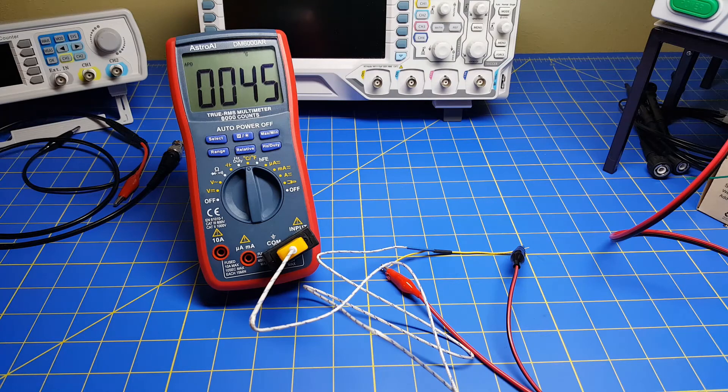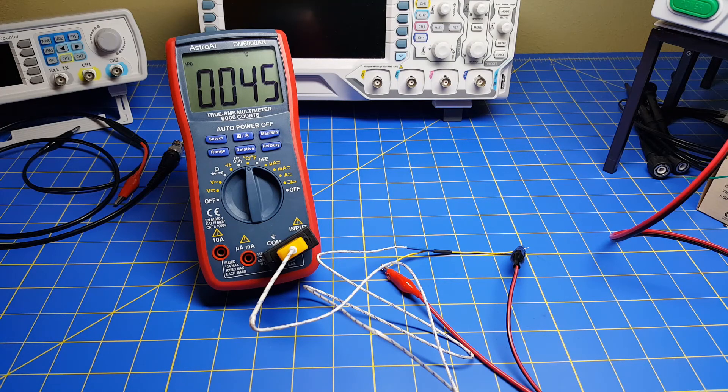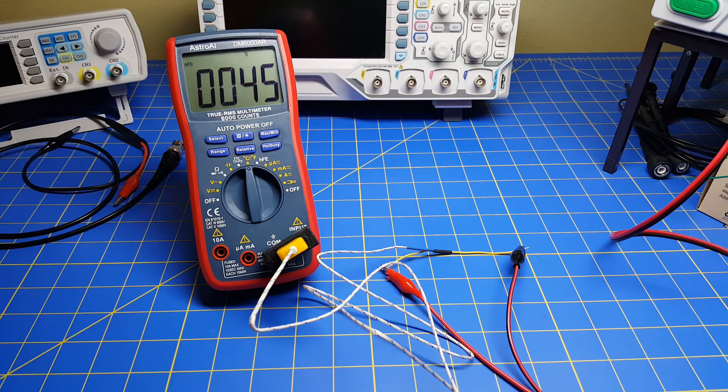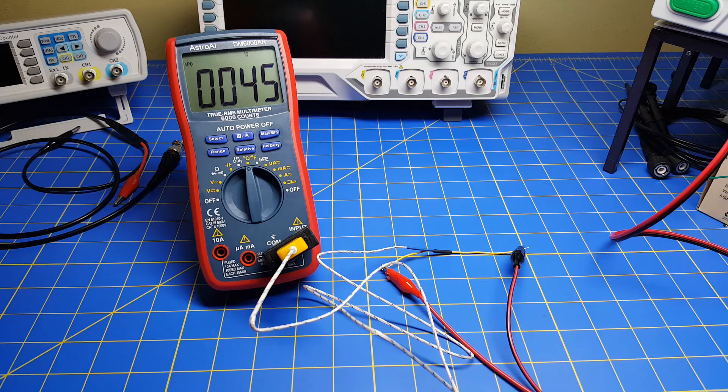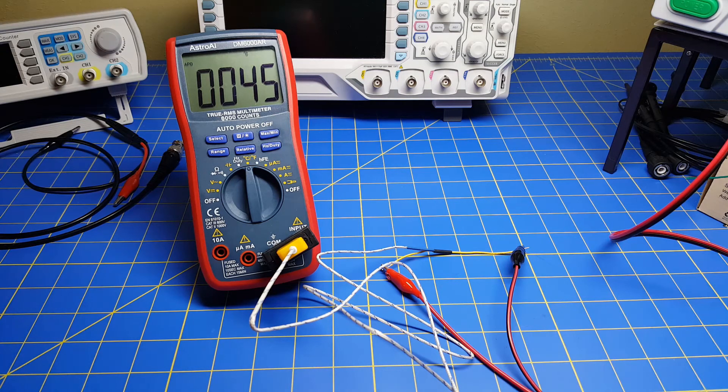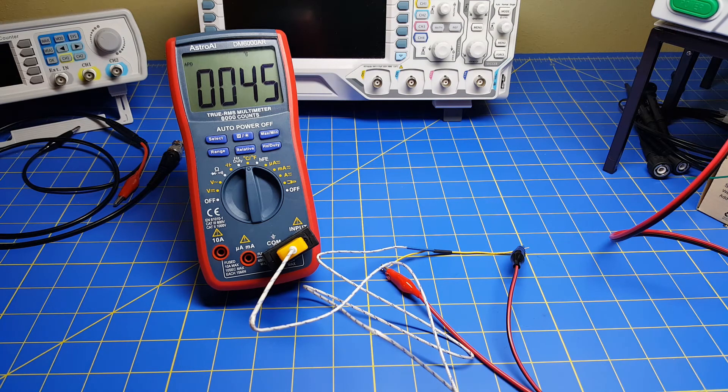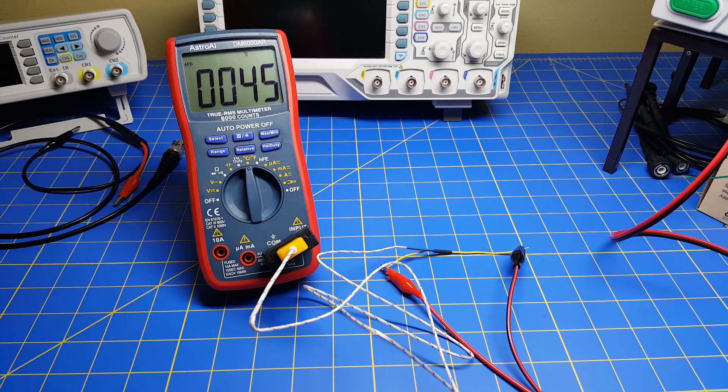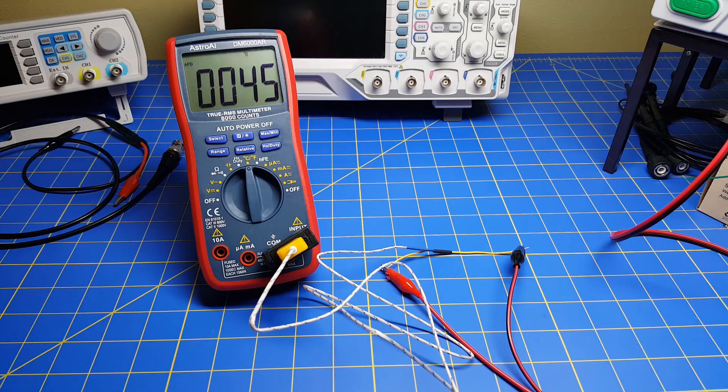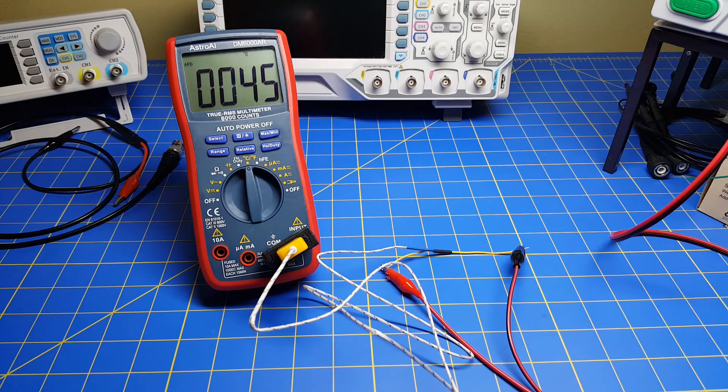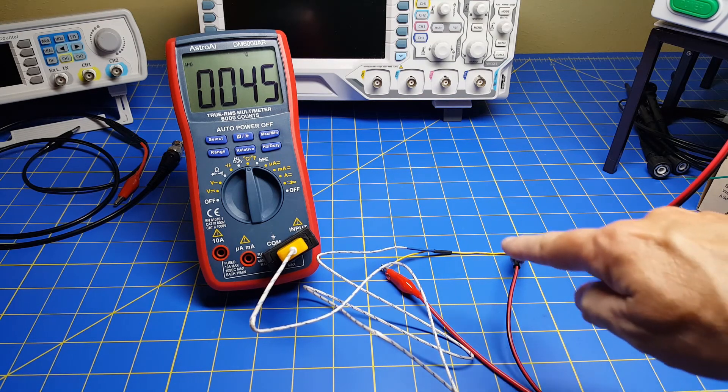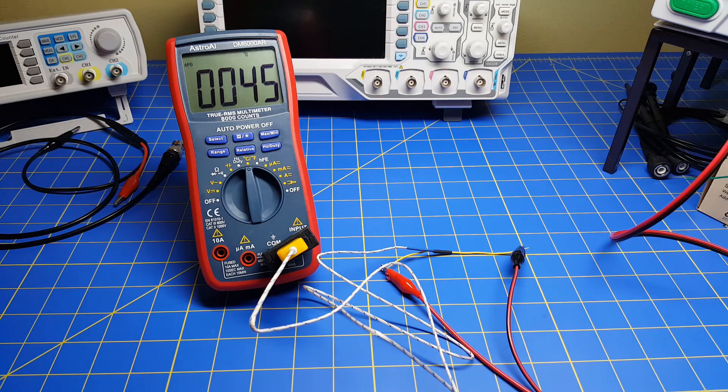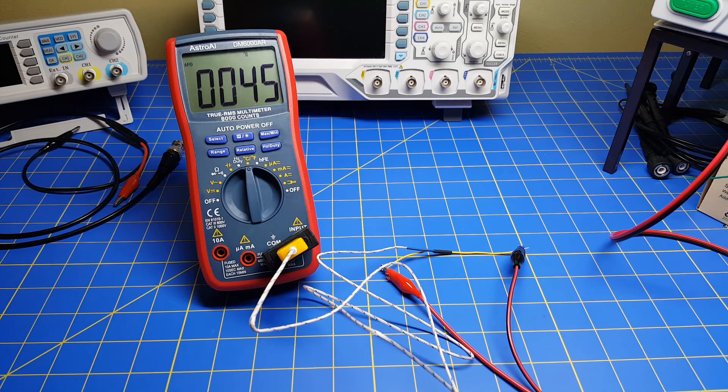Okay, so here we are after about 4 minutes or so. And the temperature has pretty much flattened out around 45 degrees centigrade. Once in a while it bounces up to 46. But, as you can see, it's nowhere near the 80 degrees C that the 8 amps are supposed to give you, which is the rating of the PVC. So, interesting. Now, you can also notice that the wire is not melting, it's not burning, it's not smoking. It seems to be okay.